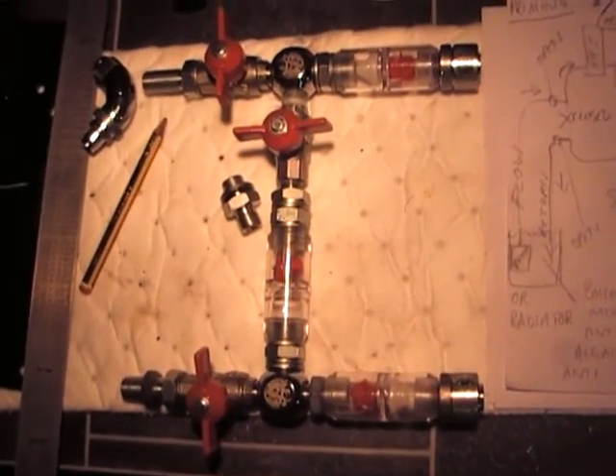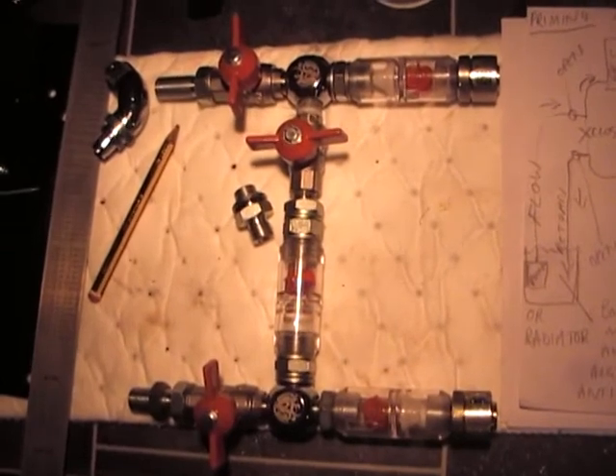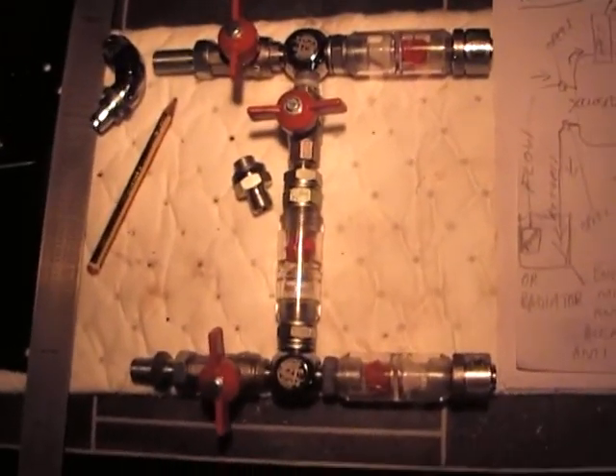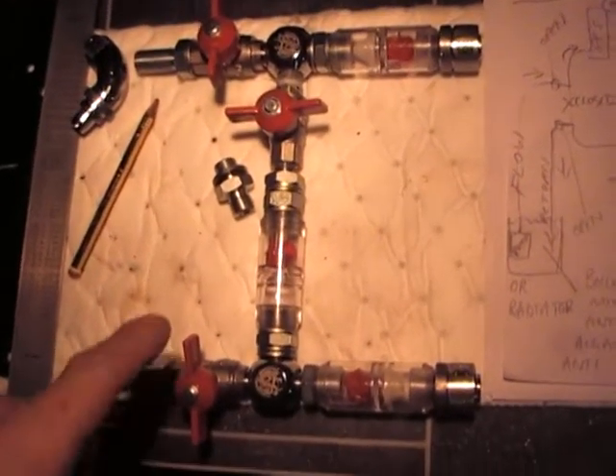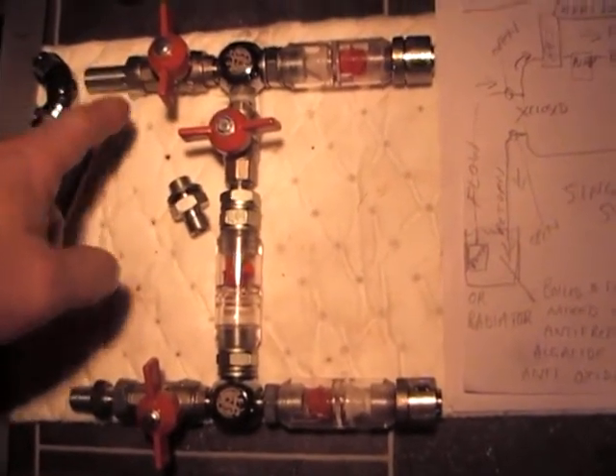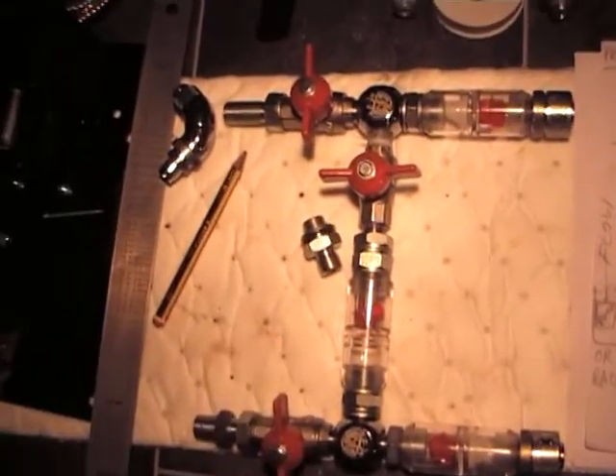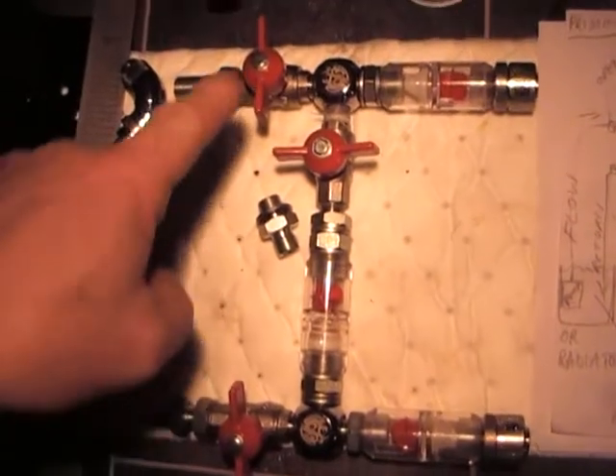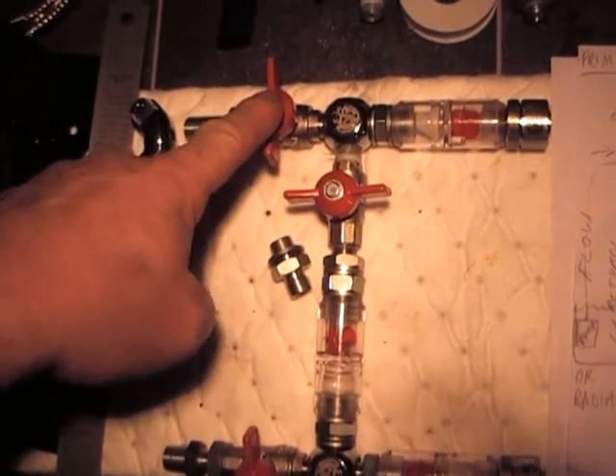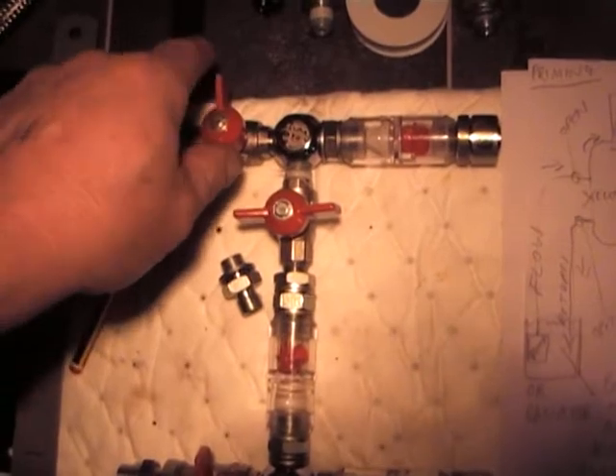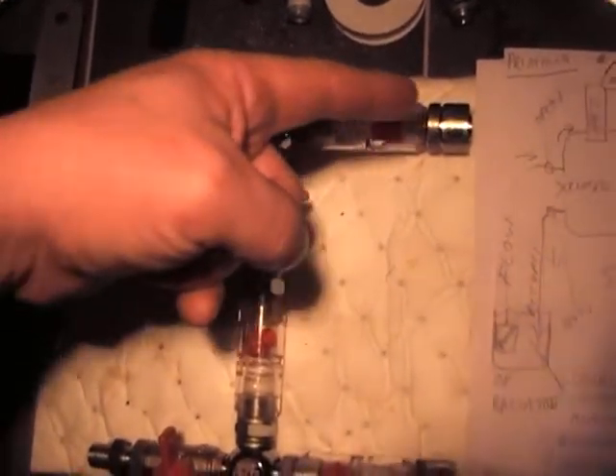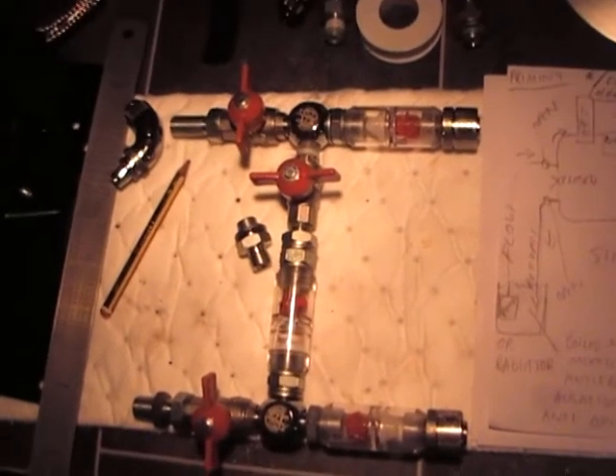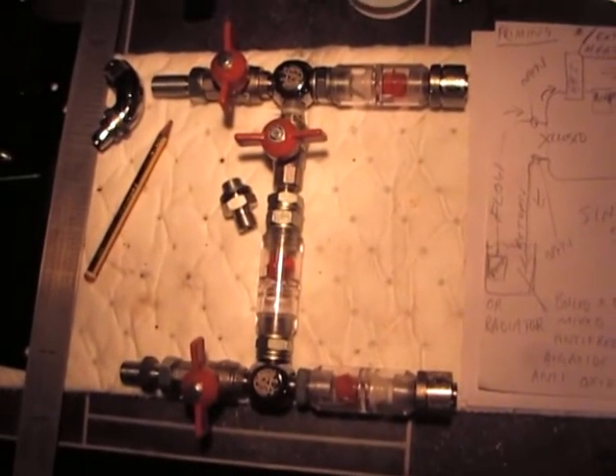One of the first water cool systems I built, couldn't get the air out of it. So what I did was I cheated a little bit. I used a hose pipe with mains pressure. And what I did was hooked it up to the flow side. This valve is closed. And then slowly, make sure this tap is open going into a reservoir. And then what I did was slowly open this valve. Really gradually open the valve and let the mains pressure get into the system. It just blew the air out no problem.